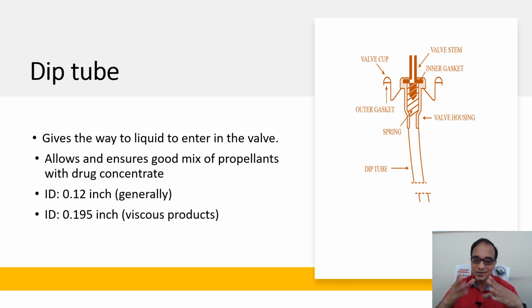Only dispensing is the work of the valve, and it ensures a good mix of propellants with drug concentrate, so no propellant can be dispensed without drug. So actually it is ensuring that not only the propellant is going alone, but the drug is also there with the propellant. So it ensures the delivery of drug along with the propellant.